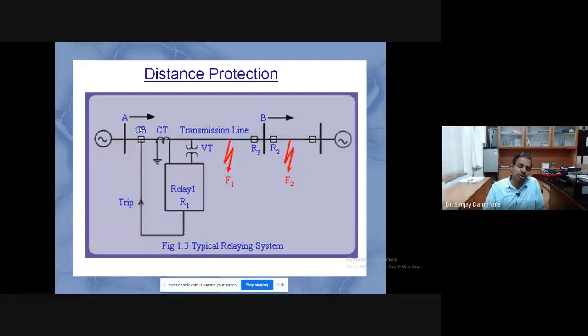So this is how the distance protection works, and there is a family of these relays like impedance relays, Mho relays. I will not go into advantages, disadvantages, but now we are talking of the most stable relay, which is the quadrilateral relay. And this quadrilateral relay characteristic, earlier it was not possible, but now it is possible to realize and simulate because of the numerical environment.